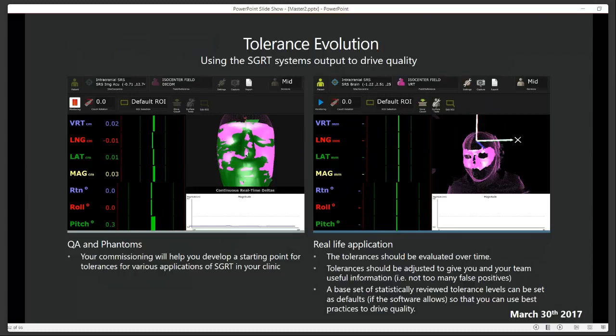We kind of open up our tolerances during that initial treatment time where we're doing easier treatments. This system allows you through a single click on a reg file to dump all of your real-time deltas to a file for every fraction, and then you can statistically evaluate those and say, okay, on a right breast, we are routinely holding 3 millimeters throughout the course of treatment. Maybe we use 3 millimeters as our standard, and then whatever false positives we get, if we need to back that off to 4 millimeters or 5 millimeters, we can. At our centers, we have pushed our breast tolerances all the way down to 3 millimeters, whether it's deep inspiration breath hold breast or just a standard breast or prone breast.